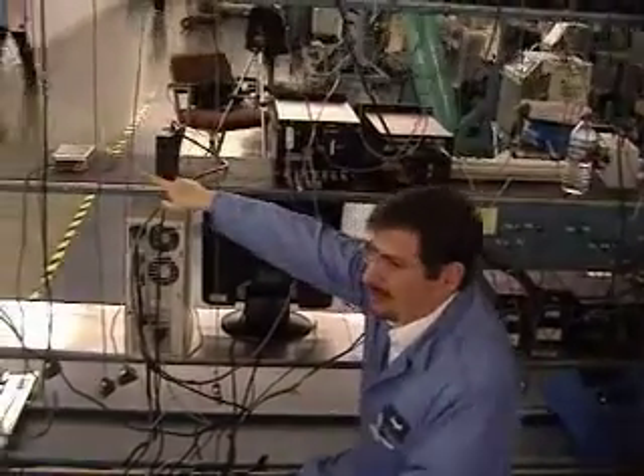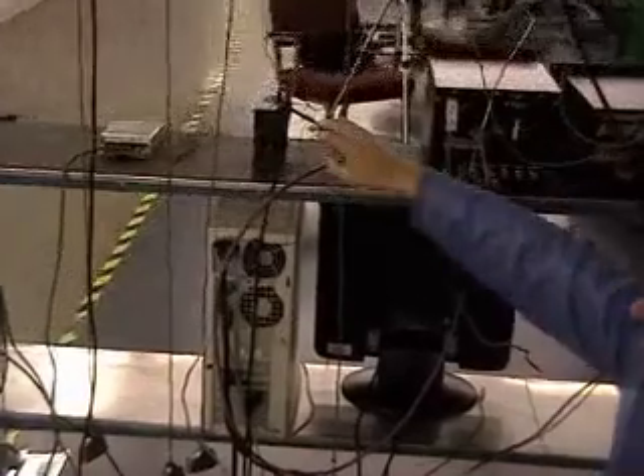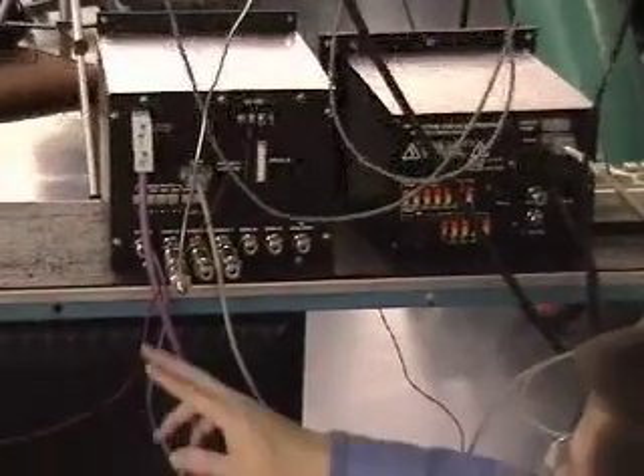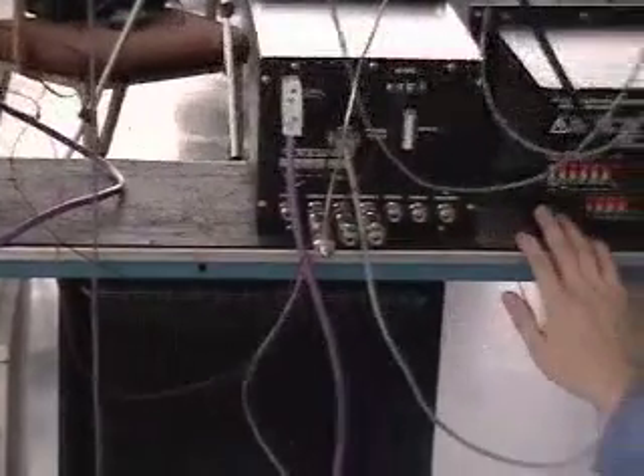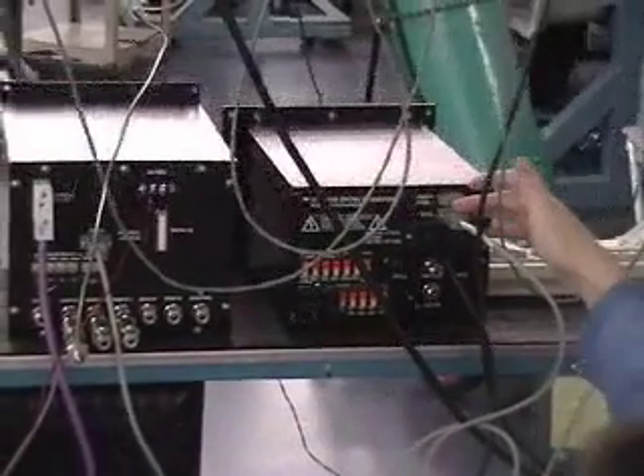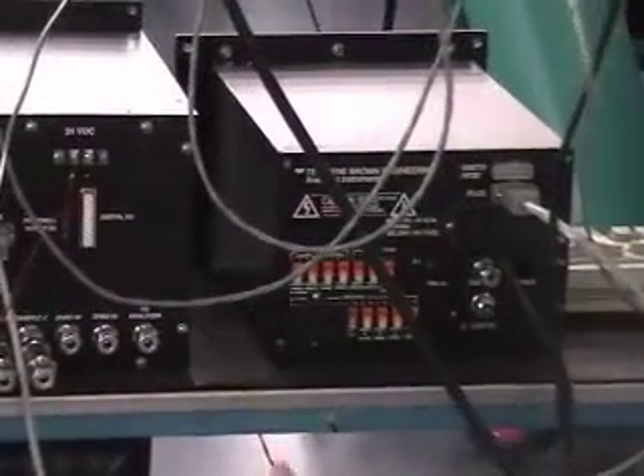Okay, this is the interconnection that we are doing on the back. We have a 24-volt power supply over there that is going to feed power to our Step 7 PLC and 24-volt power to the BB1. We get the Profibus network connection, this purple cable that goes to the Step 7. We've got the RS-232 cable that will connect to our 3000 TA oxygen analyzer. So we'll have communication between the BB1 and the oxygen analyzer. Now the Step 7 will collect data from the BB1 and send it to a network card installed on this PC. Then we can send commands through this PC to the Step 7 PLC so that we can select valves on the BB1.